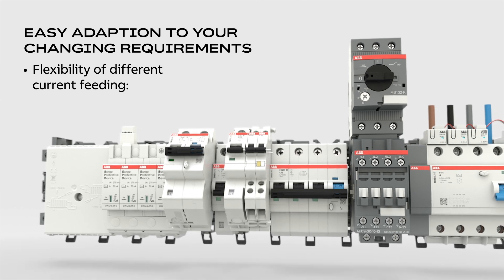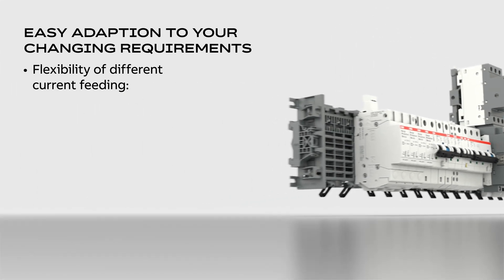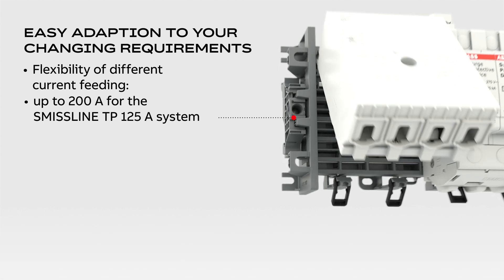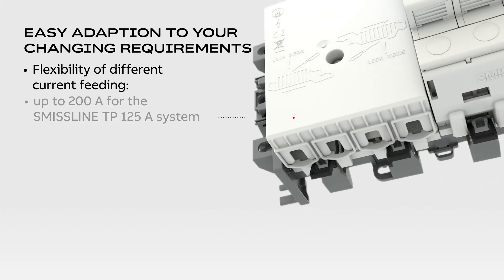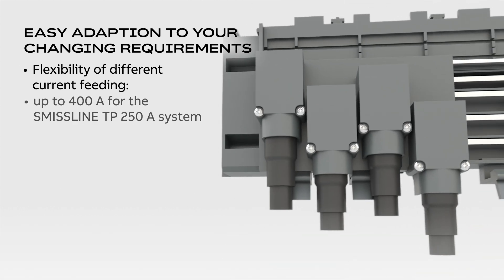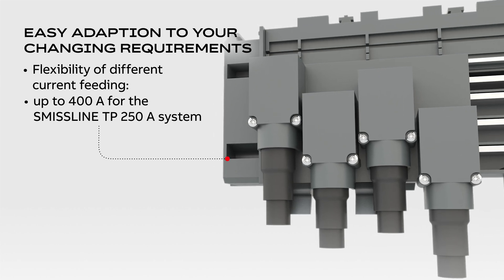The system is scalable thanks to the flexibility of different current feeding, allowing up to 200 amps for the Smissline TP 125 amp system and up to 400 amps for the Smissline TP 250 amp system. The system can be arranged horizontally or vertically.